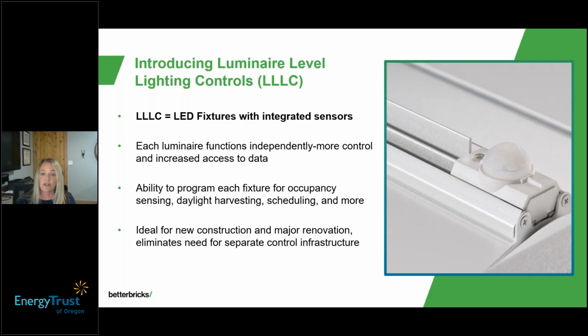For any new construction or major renovation, we don't have to do a major design around specific zones for daylight harvesting or how we want occupancy set up. We can do all that just like the fixtures are hardwired, but without designing it - we can just order every fixture with that LLLC capability and enable it in each area where we need that. So it gives us a smart building, if you will, without any additional wiring, centralized controls, or additional cost in a lot of cases.